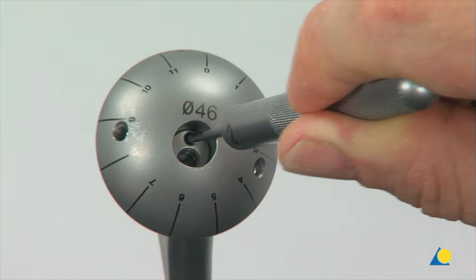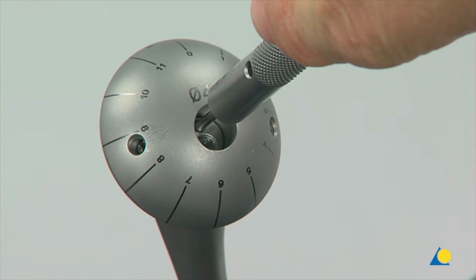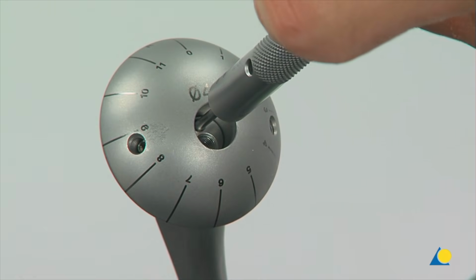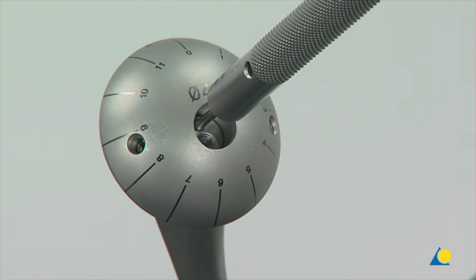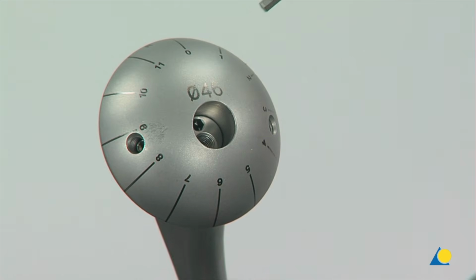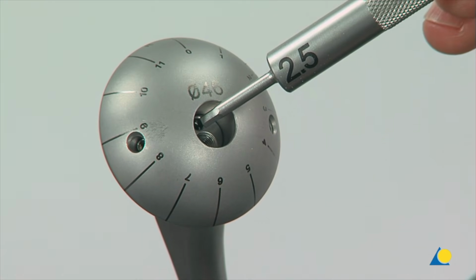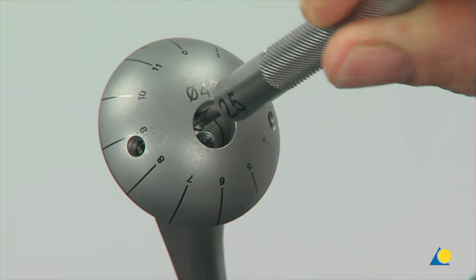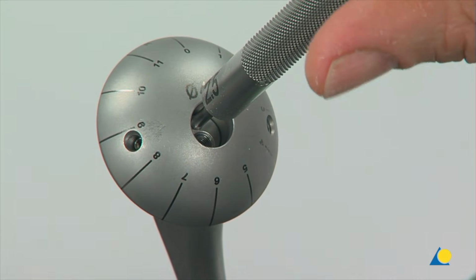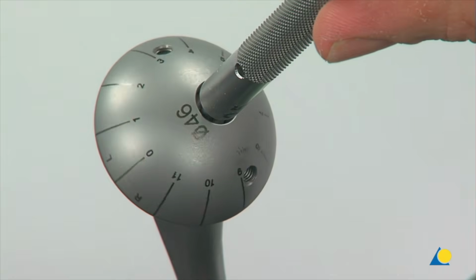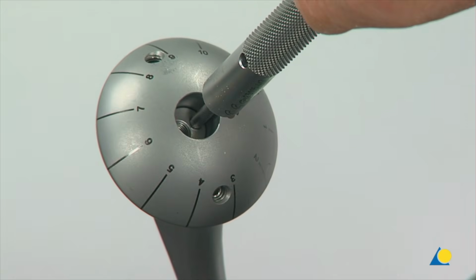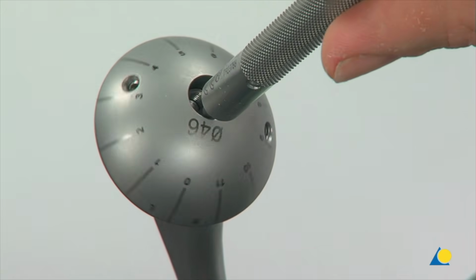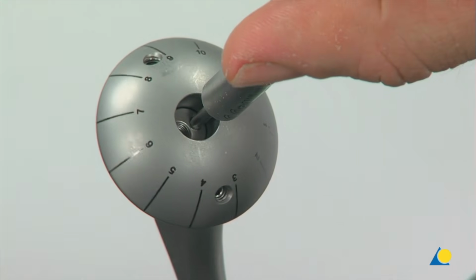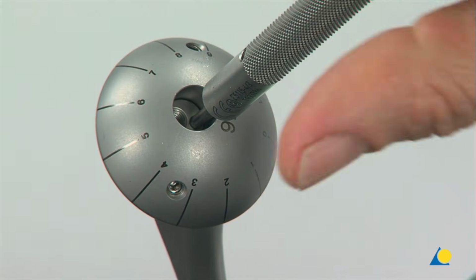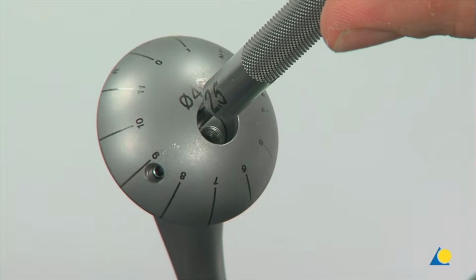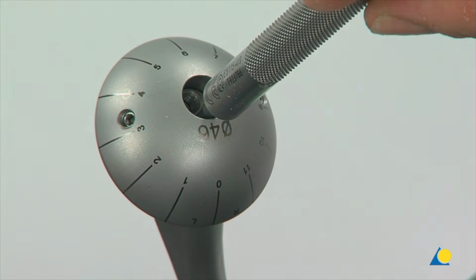The trial eccenter is loosened with the 2 mm hex screwdriver. The 2.5 mm hex screwdriver is used to rotate the trial eccenter until the desired position of the head is achieved. Note, the 2 mm hex screwdriver is used for locking and unlocking the set screws and the trial eccenter. The 2.5 mm hex screwdriver is used only to rotate the trial eccenter.